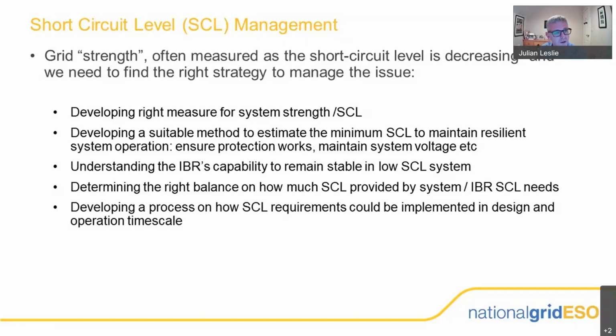That's what we're working through now - understanding what the right solution is, how you get there, and how you ensure pre-fault that actually if the fault were to happen, enough short circuit infeed would be available on the network, such that it's stable and that the protection systems and everything else work as they should. So it's a really interesting piece of work.